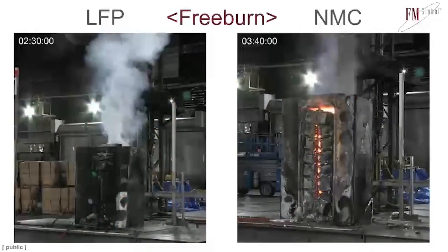Something else that's unique about the NMC is what happens towards the tail end of the fire. Mind you, these are battery fires, and batteries are going into thermal runaway, and they're venting an ignitable gas, or a flammable gas. What I've noticed, which was surprising during these tests, is that you'll have all this active flaming coming outside of the energy storage system, and then at some point in time it can just stop. All of the flames just disappear. And you might think that that's extinguishment, but particularly with the NMC system, we had what we thought was extinguishment, and then slowly over time, and this can go on for hours, the temperature inside, as we're measuring temperatures in there, continues to increase.